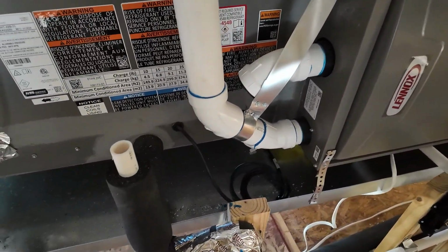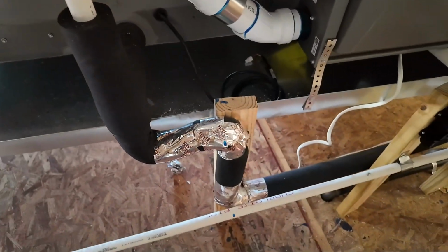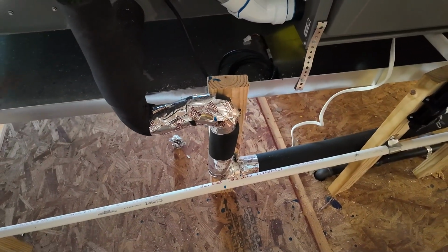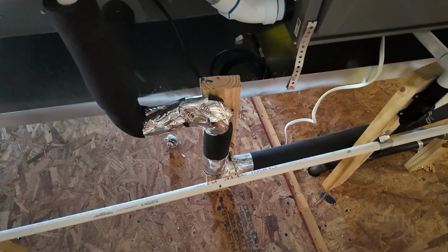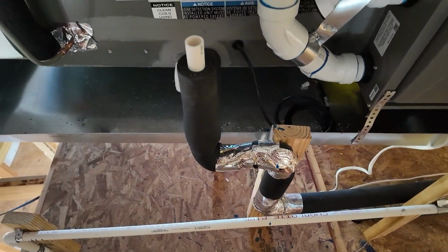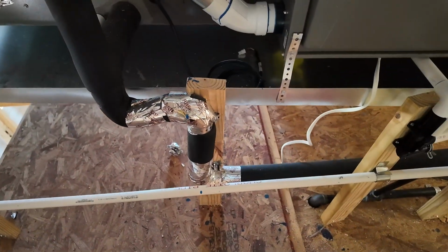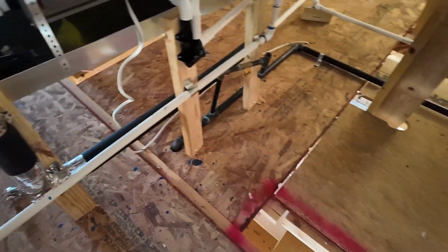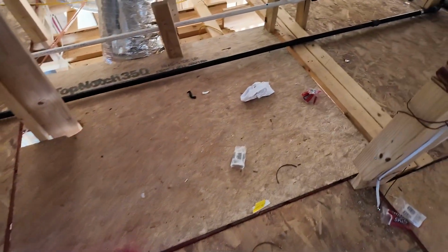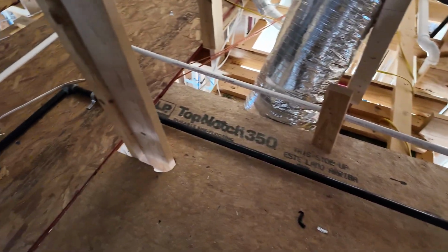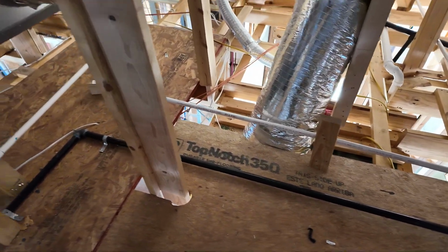Now, you'll never smell it because it'll be so diluted, but all your pathogens and your cooties and all those things, there's nothing to keep them from crawling up out of the sewer and getting into your attic and getting into your living space. That's why we don't have shallow P-traps. You want cooties in your air? I don't want cooties in my air. Okay. So coming on along over here.